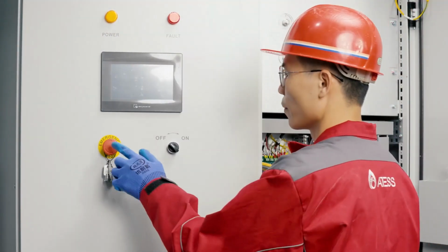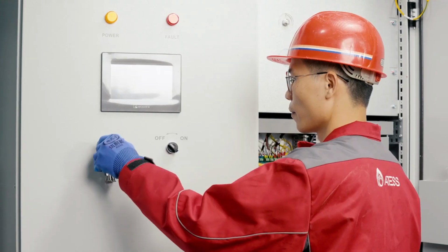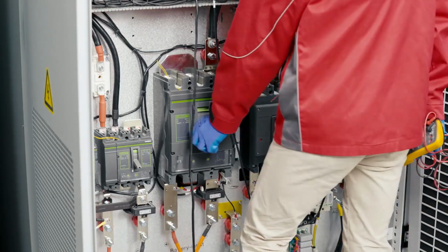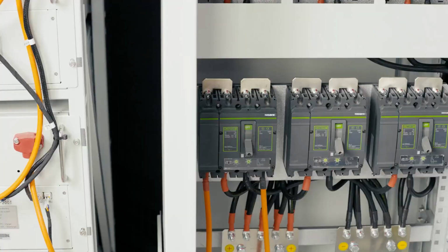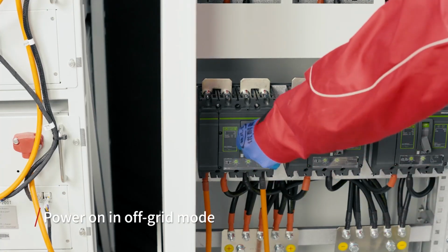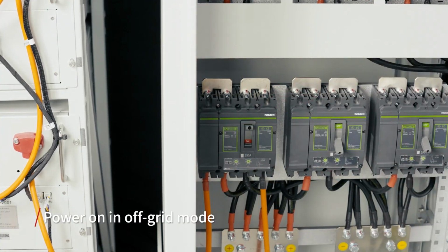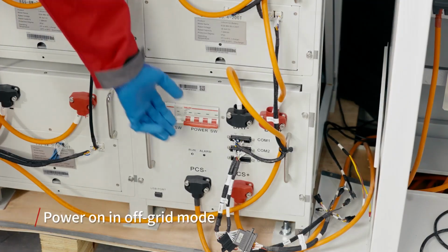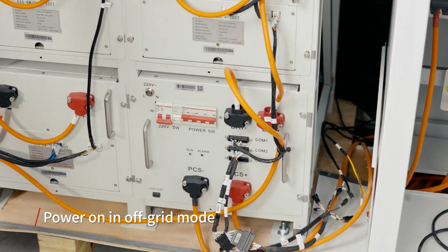Switch the red emergency stop button on the front door to unlock HPS. The button is generally pressed down before delivery. Turn on the breakers for battery and HPS, and only turn on the battery breaker of HPS. Ensure that the other breakers are disconnected.